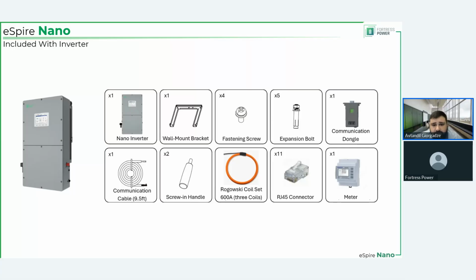So even if you change the 600 amp CTs with bigger CTs, provided that those are the CTs that you have requested from us and we have provided to you, and those are the CTs that are listed on the certification, you are retaining that UL 3741, right? Those CTs do not connect directly to the inverter, though. Those CTs connect to the meter, and the meter communicates to the inverter. And that's how that thing works.